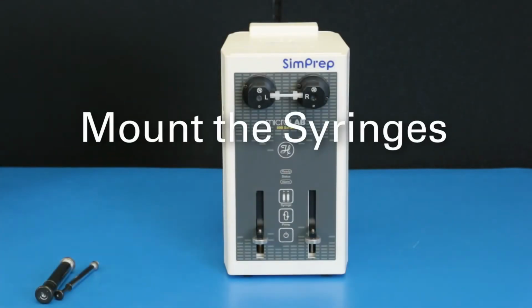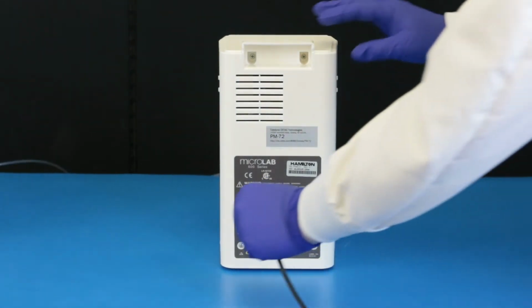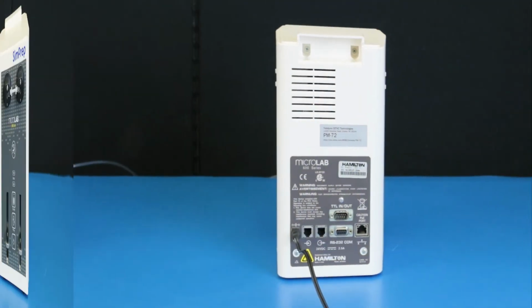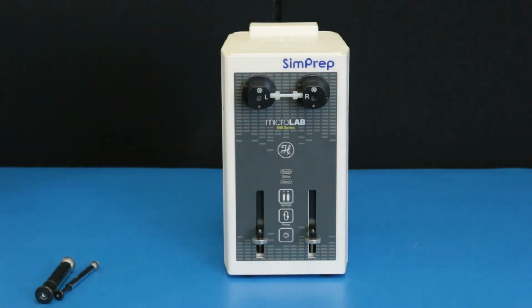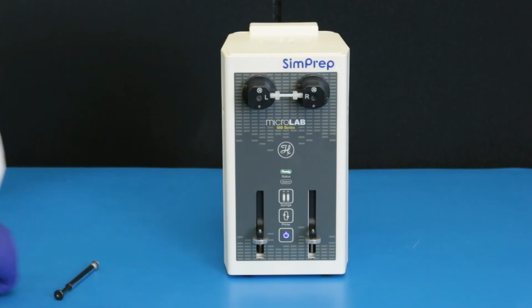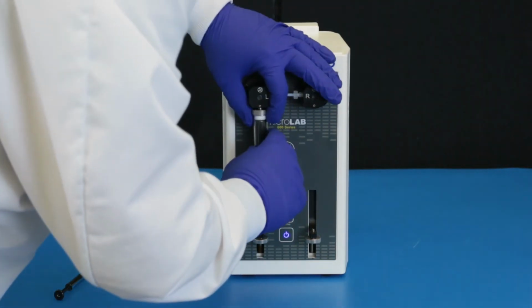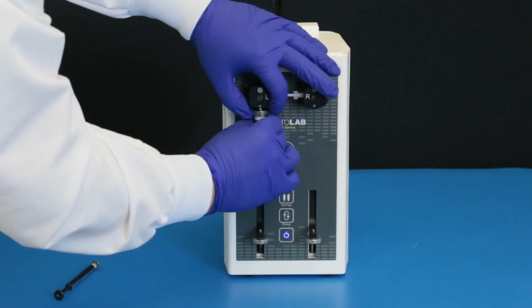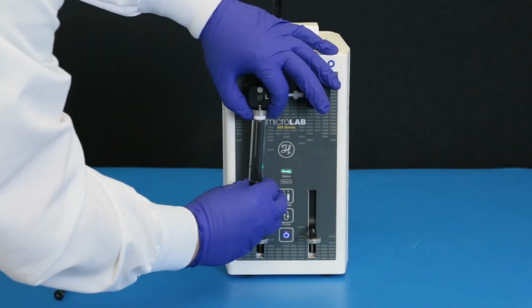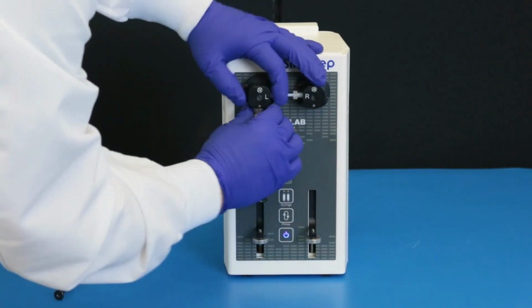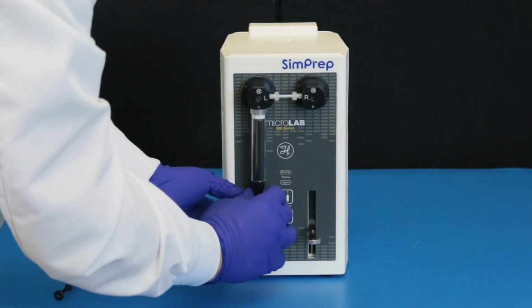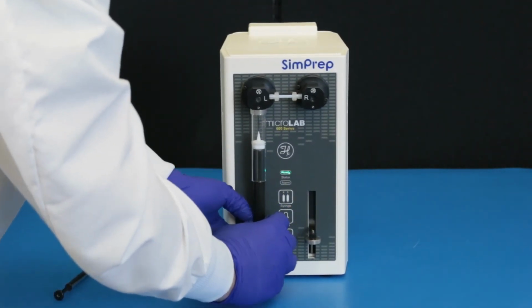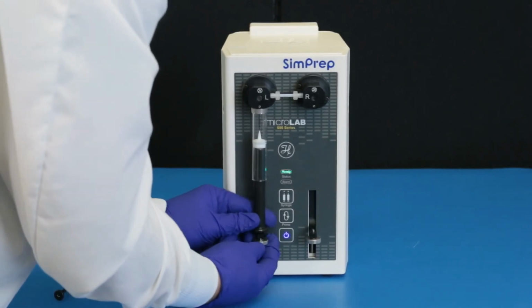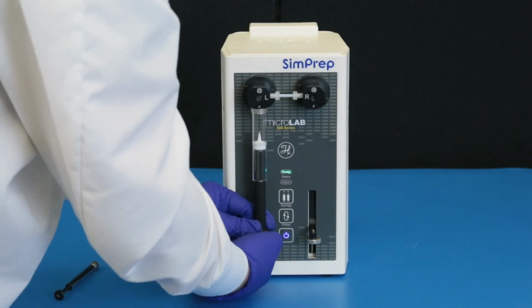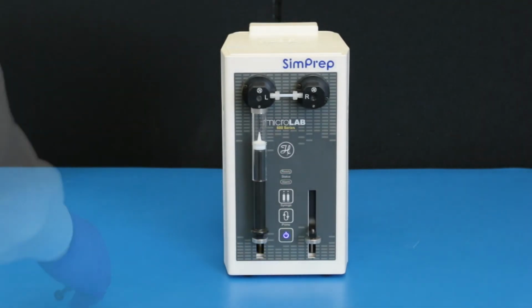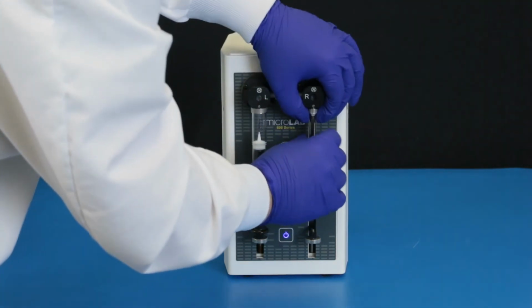Mount the syringes. Begin by plugging the power cord into the back of the syringe pump module. Power on the unit. Insert the end of the large syringe into the port on the bottom of the left valve. Turn the syringe to screw in place. Pull the syringe plunger down to meet the thumb screw. Tighten the thumb screw to secure the syringe. Repeat this process with a small syringe on the right side of the module.